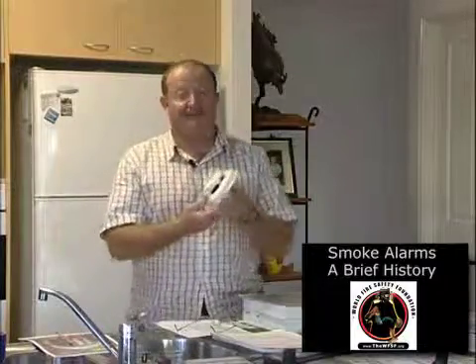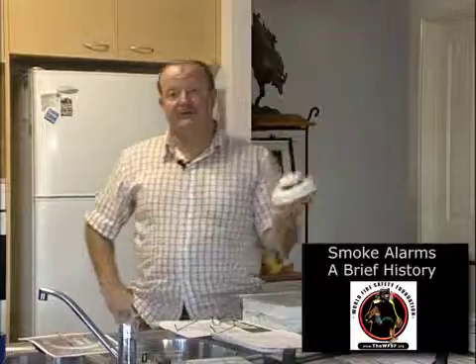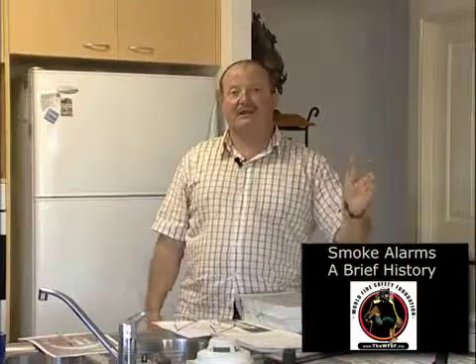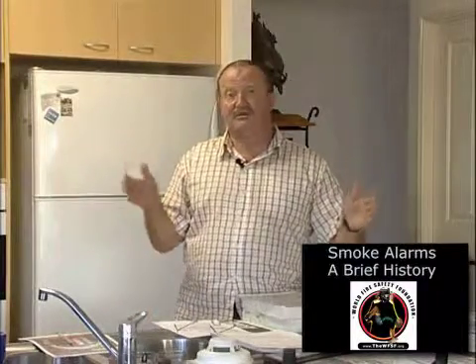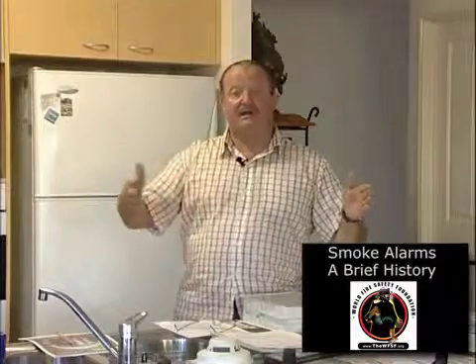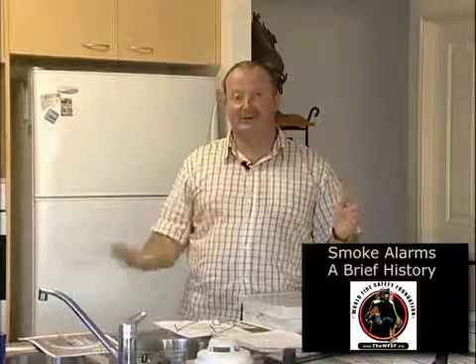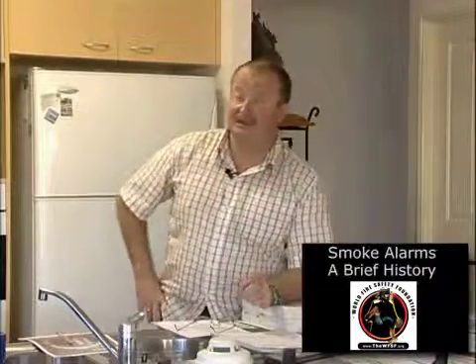15 or 16 years later, in 1951, the first patent was lodged for a photoelectric smoke alarm. We've got a photoelectric alarm here, and how these worked was a simple process. You have a light source shining on a photoelectric cell, and when smoke broke through the light source, it would actually trip the alarm. It's very similar to when you walk into a shop and set off an alarm by breaking the beam of light — same principle. But you actually had to have smoke to trip it off, which is why photoelectrics hardly have any false alarms.